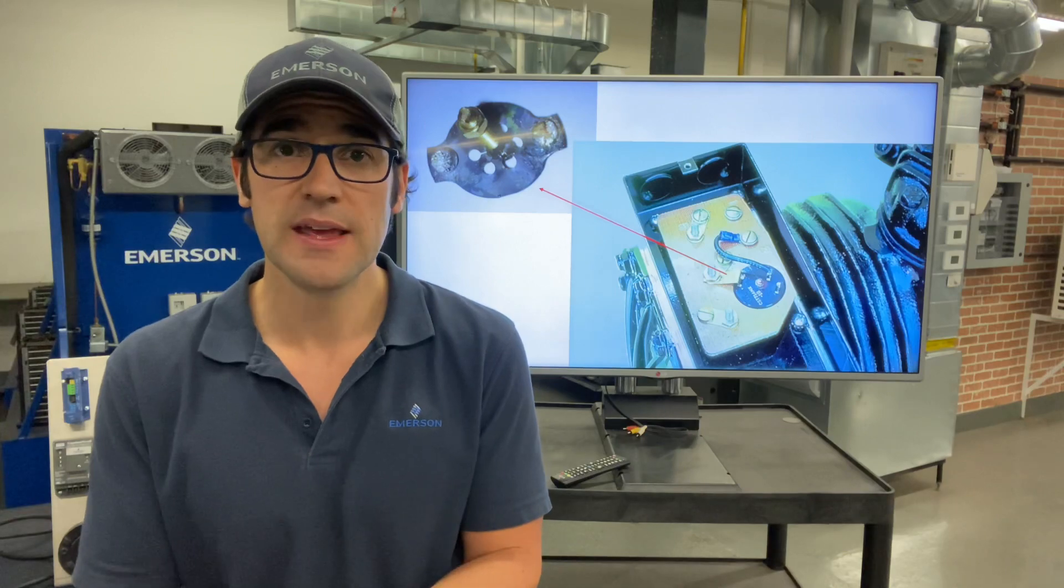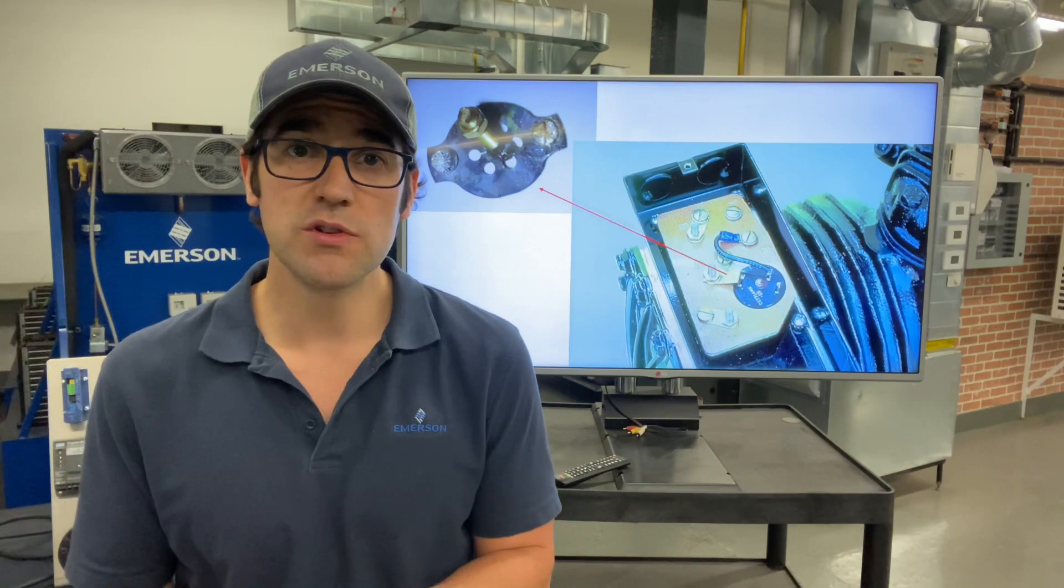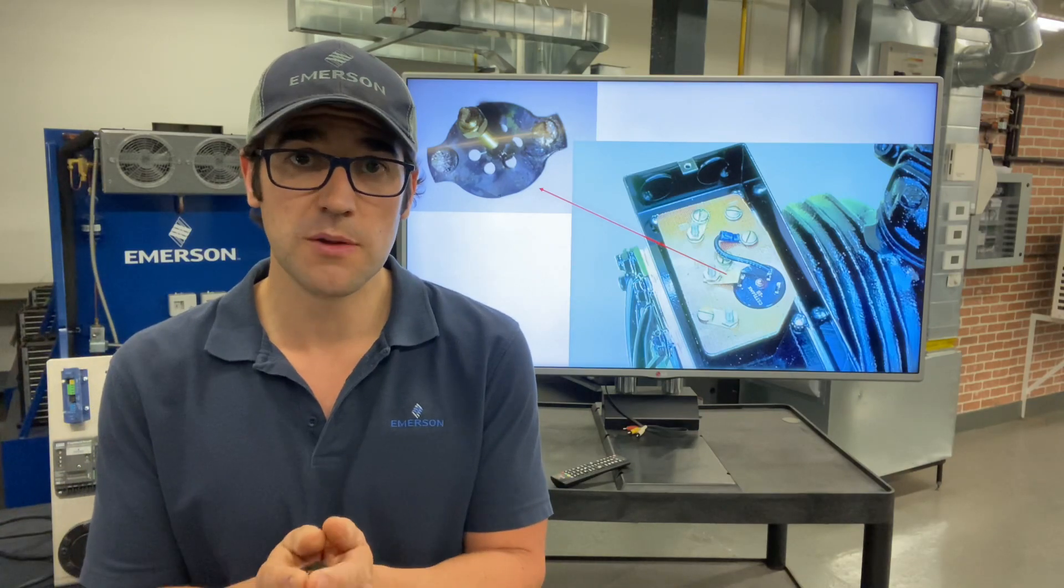Some overheating happening and when he tore apart the external protector like you see in the top corner there, it was badly pitted and possibly could have been welded.